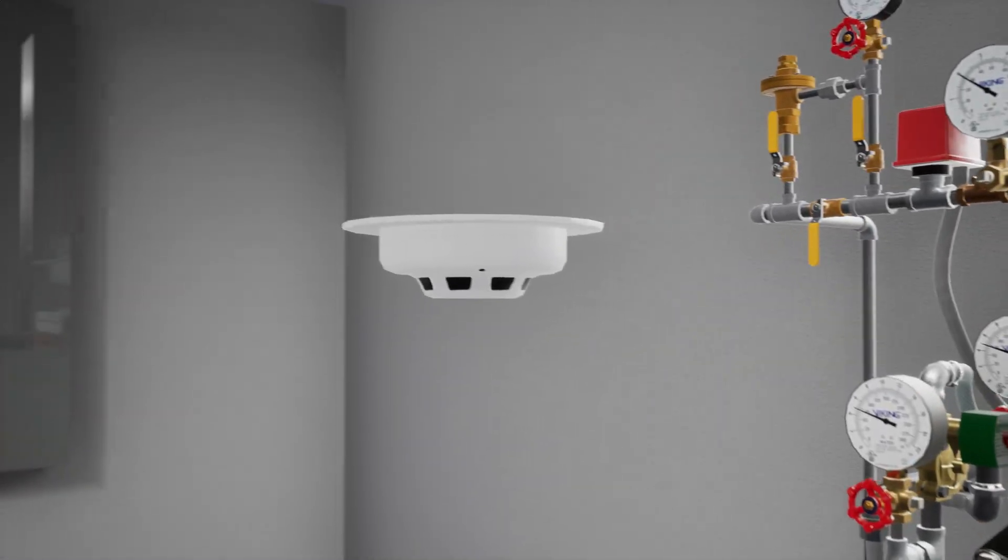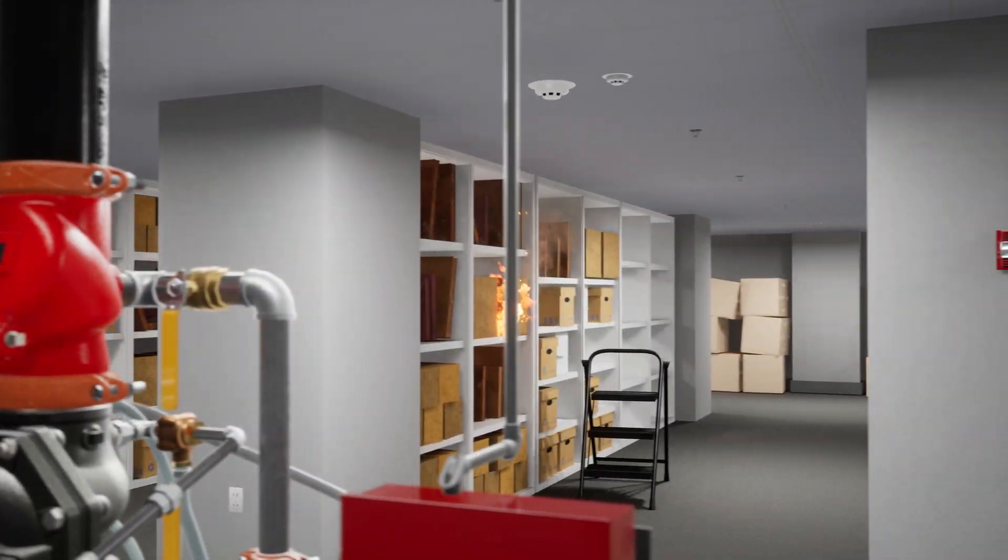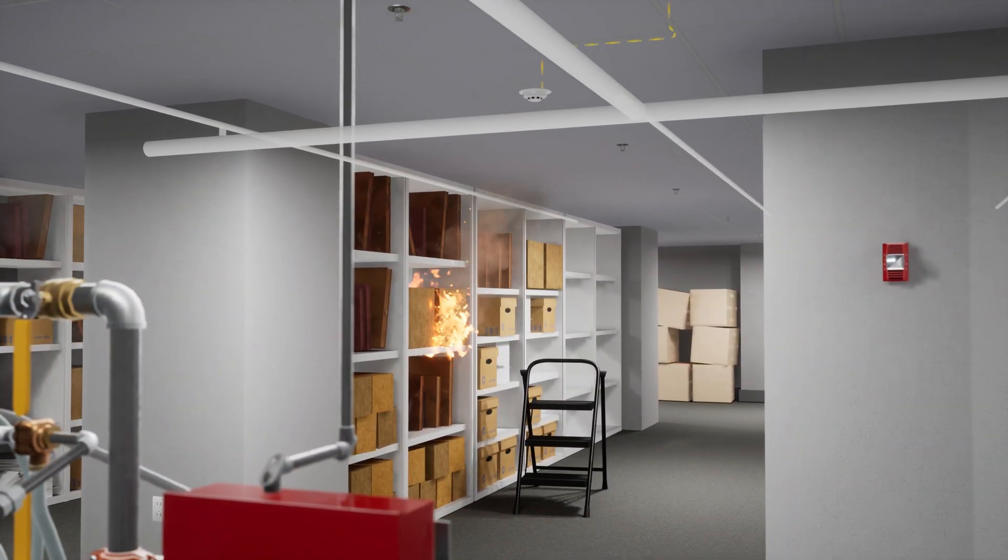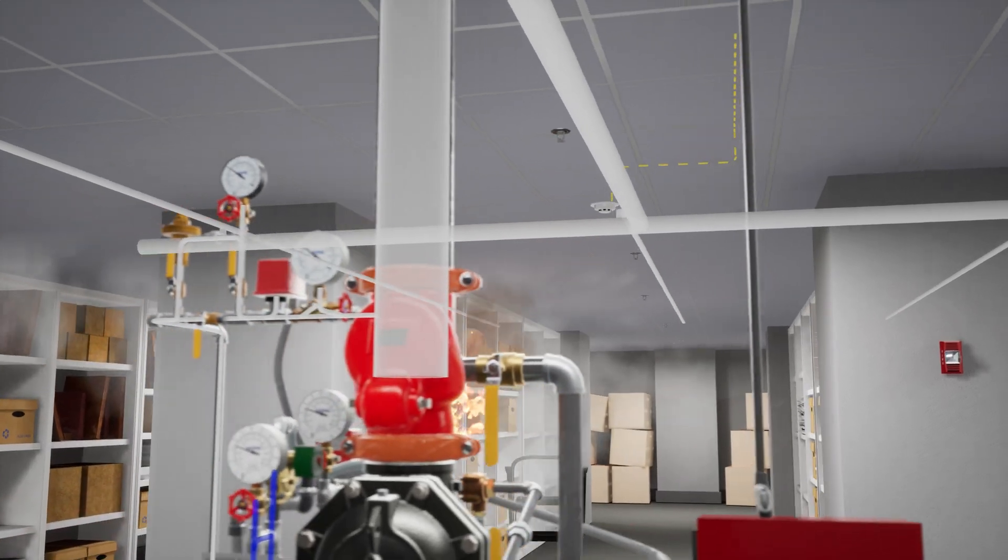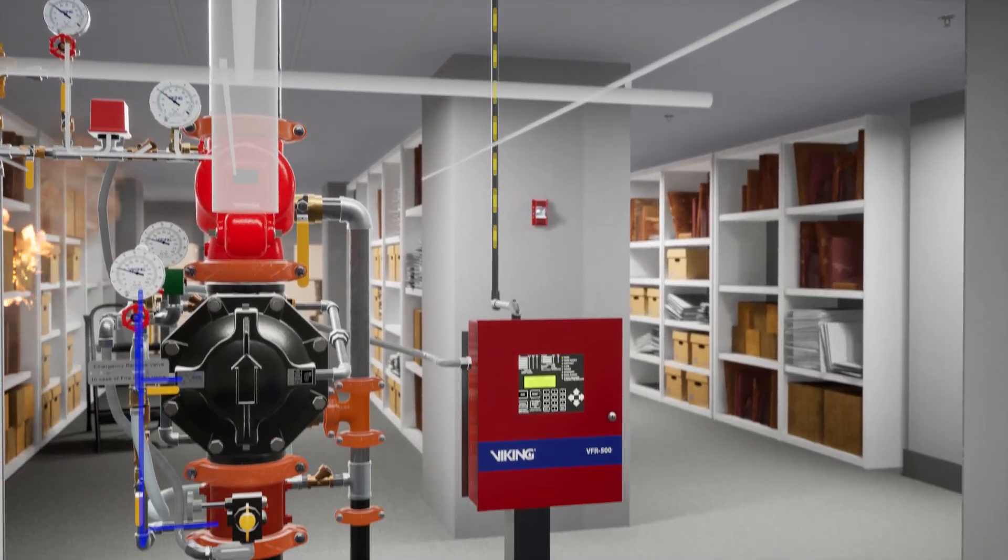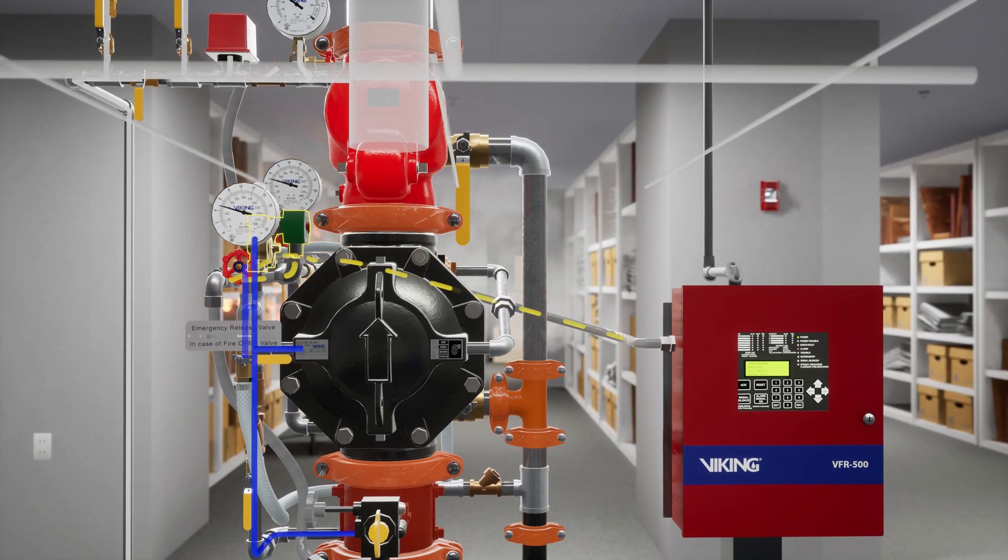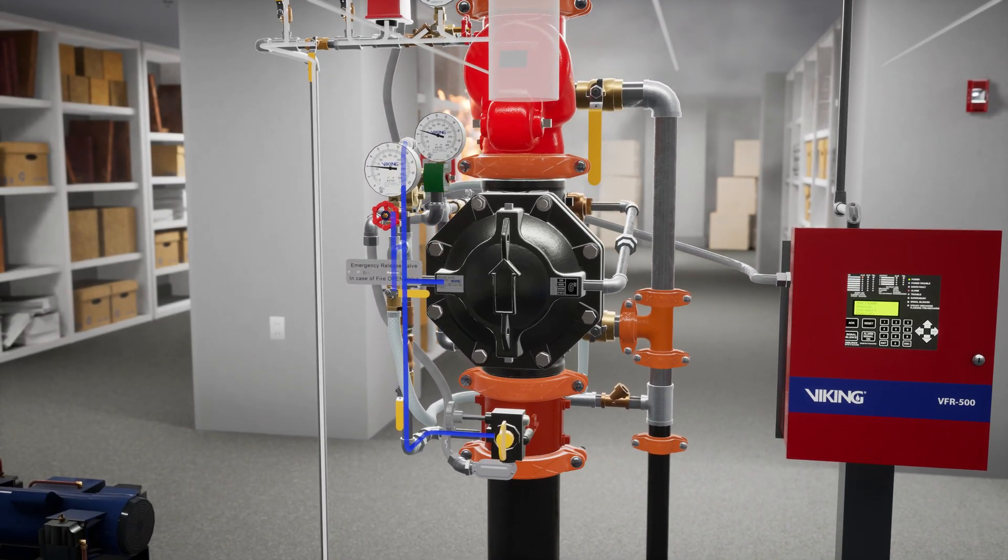The electric detection devices in this scenario are smoke detectors. In a scenario where a fire has started and begins to smoke, the smoke detector sends a signal to the VFR 500 release control panel. Once the signal is received, the VFR 500 sends 24 volts of electricity to the normally closed electric solenoid valve and powers it open, releasing water pressure from within the priming chamber of the deluge valve.